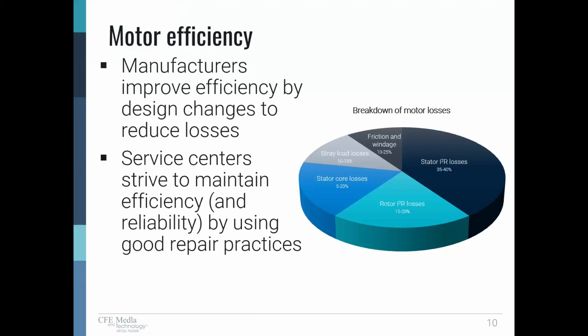And we have stator core losses to deal with. In order for the stator to work, we need a magnetic material to create the magnetic field, and that's the core. So that's another area that's, again, a big chunk of loss potential. I'm going to skip over stray load just to touch on friction and windage. That has to do with friction in the bearings, and windage from cooling fans within and even external to the motor.